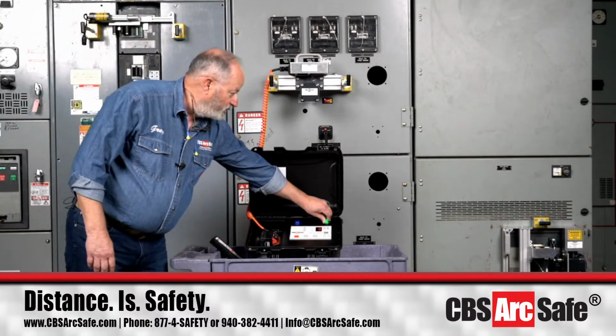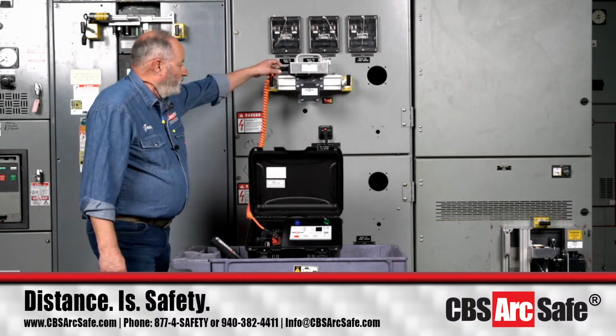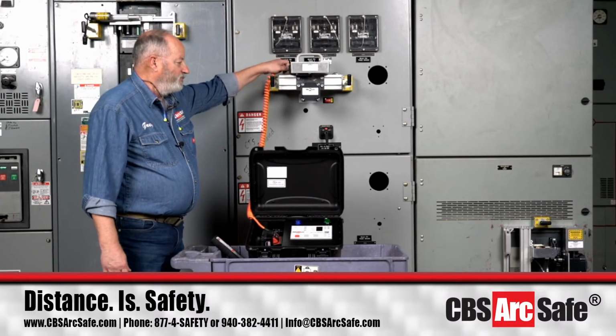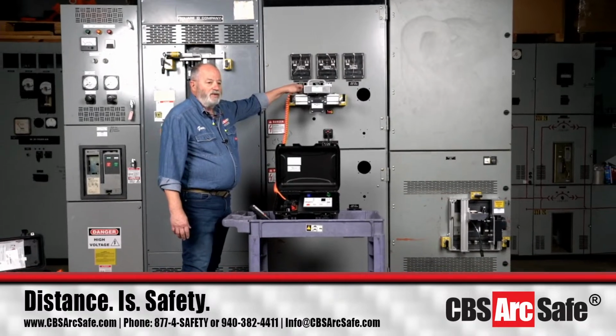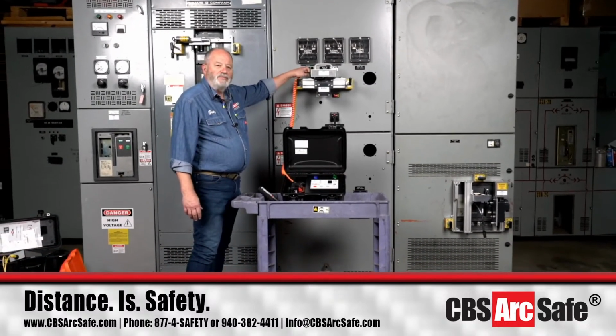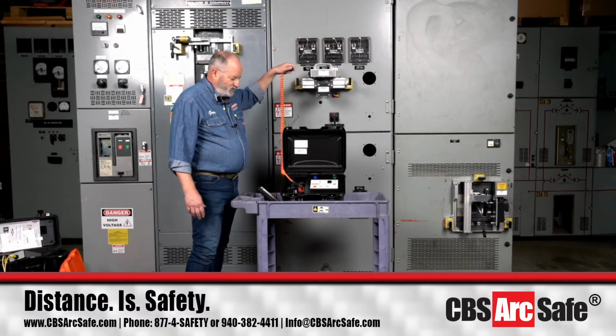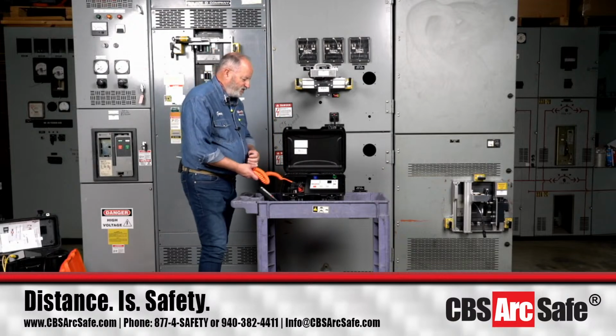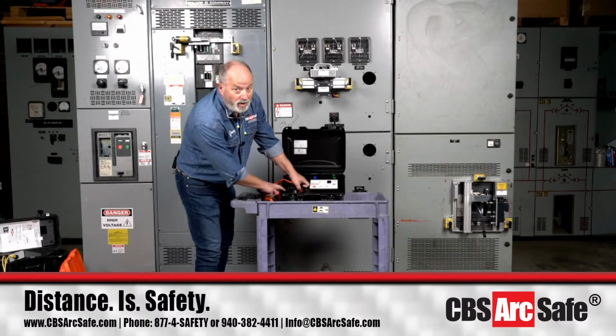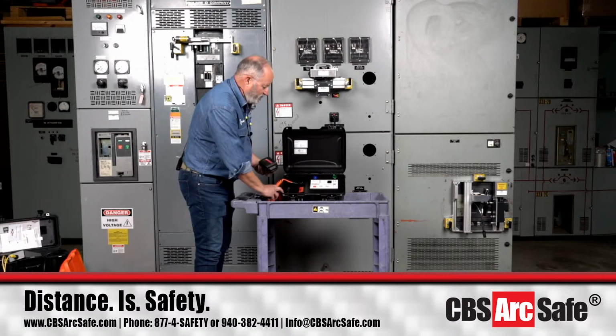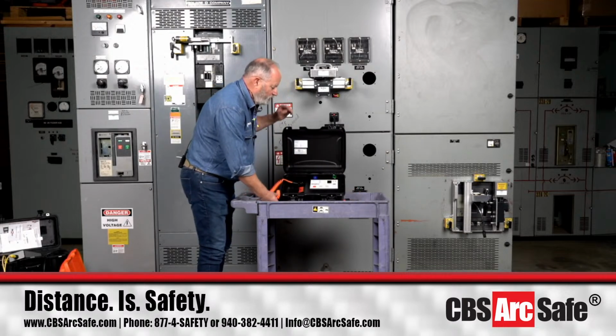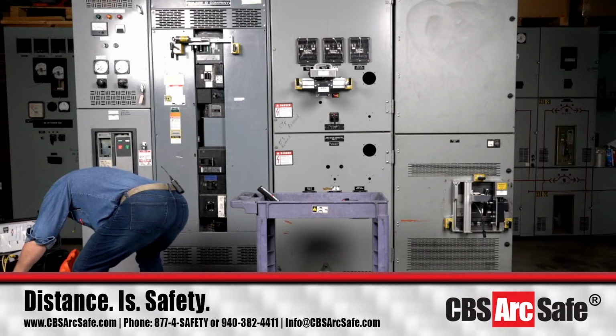The last thing we're going to show is the charge, close, and trip for the Masterpact breaker. Now, the difference between a Masterpact and a Magnum DS breaker is this: the Magnum DS breaker has a fixed stop, and when you try to exceed it, you're going to break a handle. The Masterpact breaker will actually allow you to go to the end of your strokes.